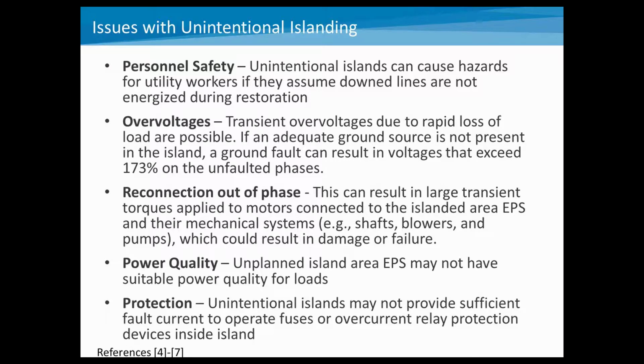In addition to that, there's also ground source issues. Ground faults can present and result in voltages that exceed 173% on unfaulted phases. So those are things that need to be addressed in terms of the grounding for distributed generation devices when you look at potentially how you could create islands in those systems. Another issue is reconnection out of phase. One thing that could potentially cause an island is the opening of a breaker or a recloser. If you reconnect that system back to the grid, potentially the grid and the island are out of phase with each other, and that could cause a transient torque applied to the motors, which could result in damage or failure. So that is a potential issue.